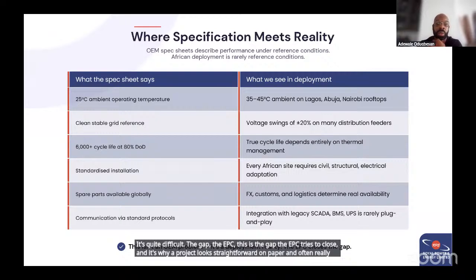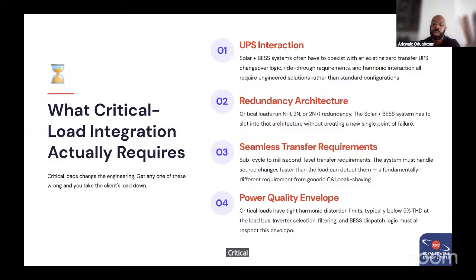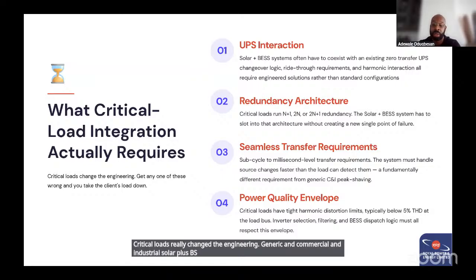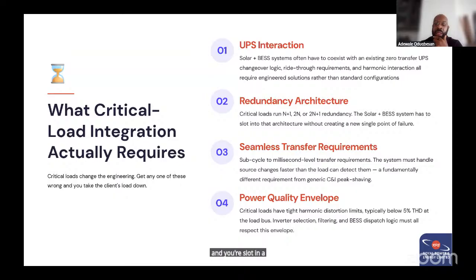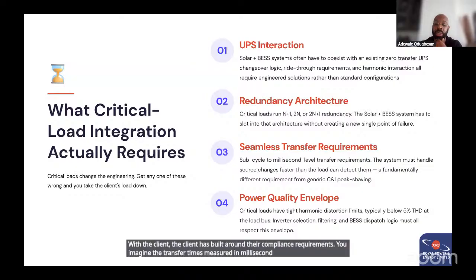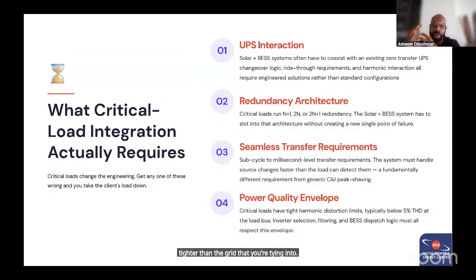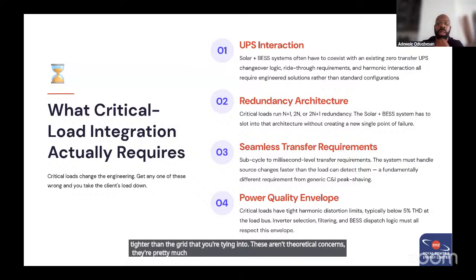Critical loads really change the engineering. Generic commercial and industrial solar-plus-BESS systems are forgiven in the C&I space, but critical loads are not forgiven. You're integrating with a UPS that might be older than your BESS, and slotting a redundancy architecture into what the client has built around their compliance requirements. Think of transfer times measured in milliseconds and harmonic distortion limits tighter than the grid you're tying into. These aren't theoretical concerns; they're practical limitations we've seen on sites trying to deploy to a number of data centers.